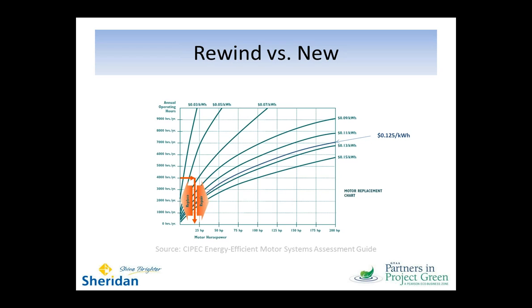So this is your cost per kilowatt hour of electricity. And again, I've put on this graph a 12.5 cents line, which indicates sort of that Ontario norm. You can see in the case of 4,000 hours that we come down somewhere around 60, 65 horsepower, if I just draw down from that curve, as this decision point on replace and repair. And so the idea then is if my motor size falls to the right of that point, I'm going to want to replace. The economics are going to favor replacement.